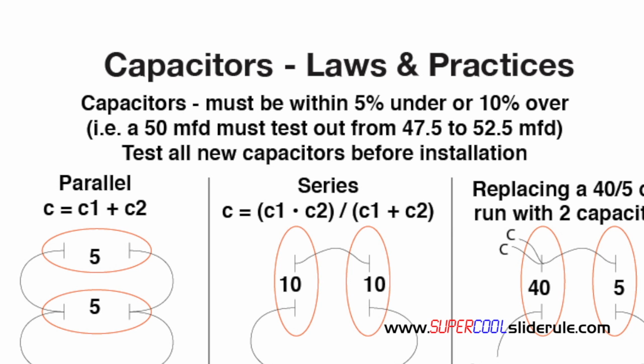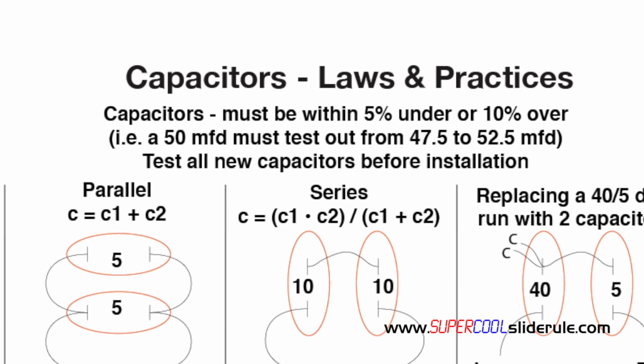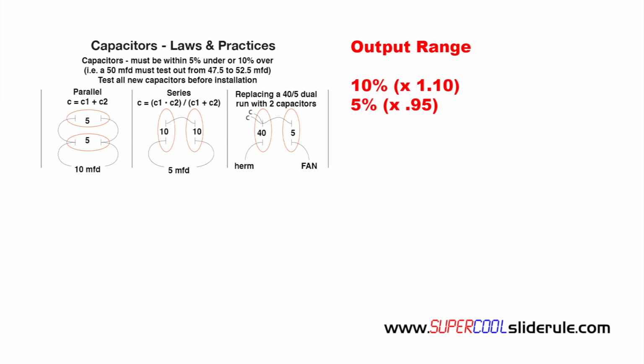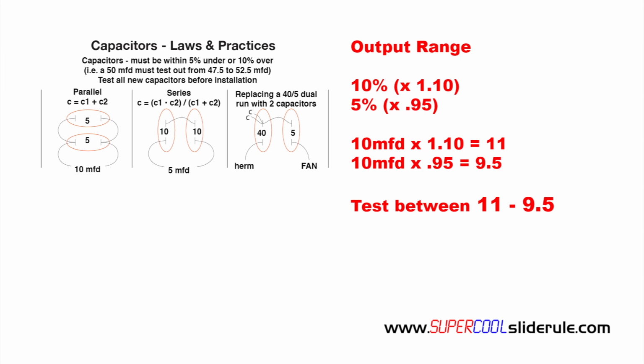The output must be no less than 5% under or 10% over. Here's the math. For 10% over, we multiply our capacitor rating by 1.10, and for 5% under, we multiply our capacitor rating by 0.95. So 10% over is 11, and 5% under is 9.5. So as long as our capacitor tests out from 11 to 9.5, it is acceptable for 99% of the applications out there.